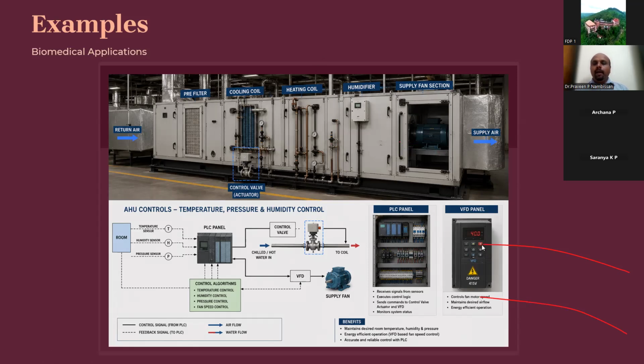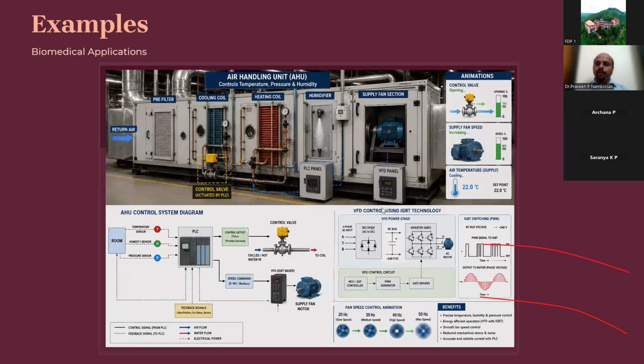Now, how will I control this? How will I control the VFD panel? When we are making the control on, I can reduce or increase the frequency. How does the frequency get increased or reduced? And what is the importance, or what is the value I will get? How will I reduce the frequency in a VFD? I can just show you that. You might have heard of IGBTs, right? IGBT. This is the same thing. In the VFD, I am just focusing on the IGBT section. The IGBT section includes the firing angle of the IGBT.